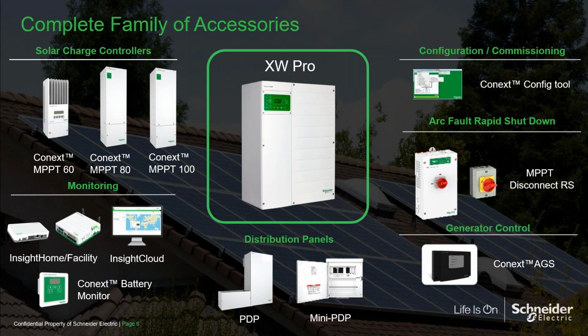Schneider Electric Solar offers a complete suite of products that are proven to offer unparalleled reliability and versatility for residential and small commercial applications. Our XW Pro platform is the latest in smart grid technology and offers UL 1741 SA compliance with advanced grid interactive functionality. XW Pro can be AC coupled with third-party PV inverters or DC coupled. We offer a range of solar charge controllers for DC coupling, including MPPT 60, a passively cooled 60 amp model with a max PV input voltage of 150 volts DC. We offer two models of high voltage solar charge controllers, which include the MPPT 80 and MPPT 100, each of which has a 600 volt DC limit for PV voltage and offer 80 and 100 amps of charge current, respectively.